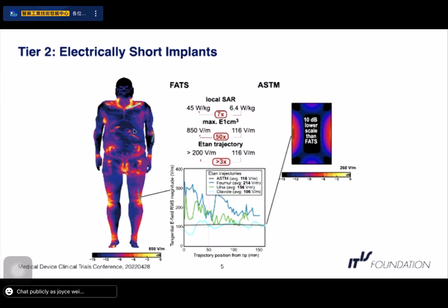Here's another summary of this. So usually in ASTM testing, you have an actual MR scanner where you place this large phantom and you place the implant somewhere on the side where the fields are a bit higher, and then you can measure the temperature. But what we do is we derive the maximum E field from the previous simulation with all the anatomical models. And then we can expose this in a simulation to the maximum average E field that we extracted from the models. And then we can relate this to temperature rise.